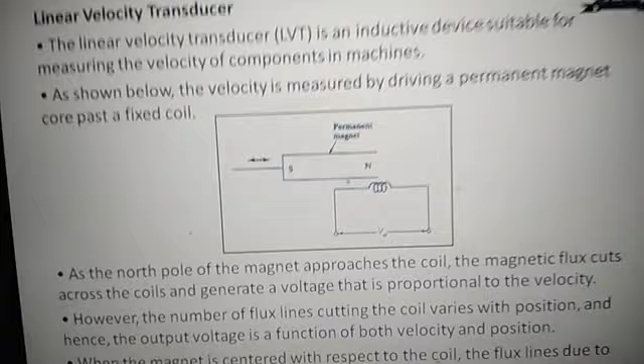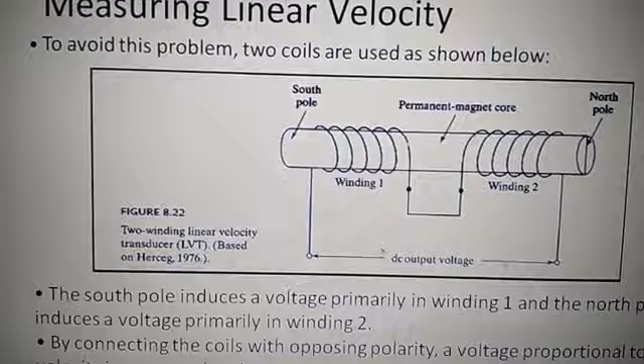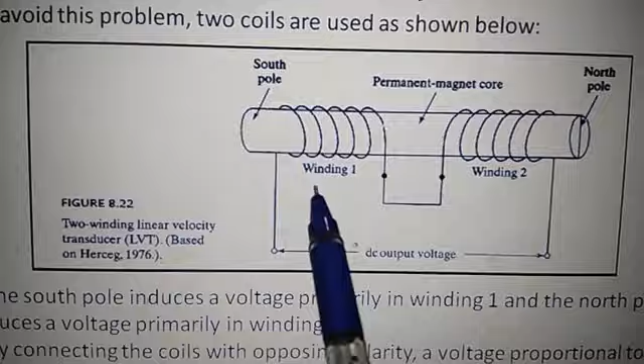When the magnet is centered with respect to the coil, the flux lines due to the south pole also induce a voltage in the coil of opposite polarity to that induced by the north pole, and the net output is zero when it is at the center. To avoid this problem, two coils are used as shown below. This is winding 1 and this is winding 2, and this is a permanent magnet here, and this is output. So when the core moves and is brought to the center, no flux linkages will be there. This is also an LVT, two winding linear velocity transducer.